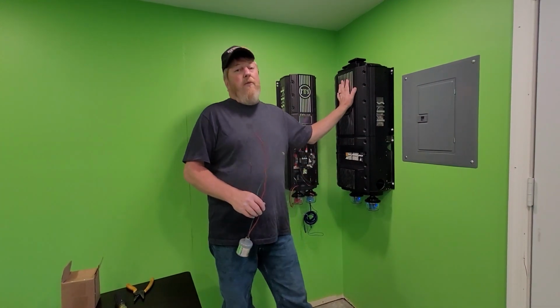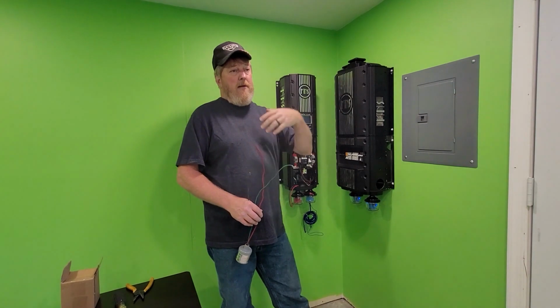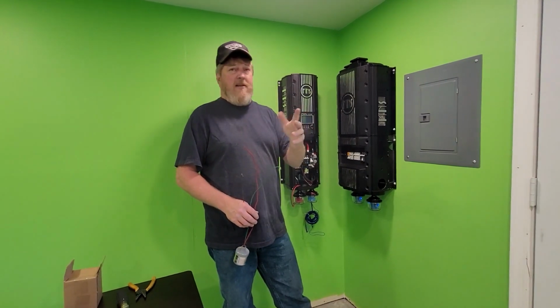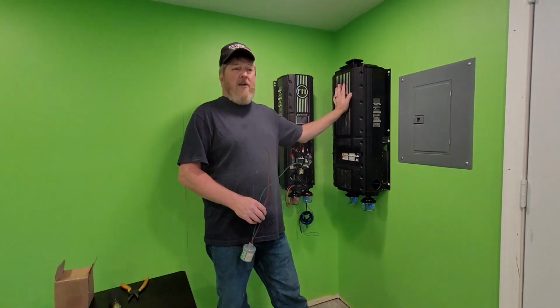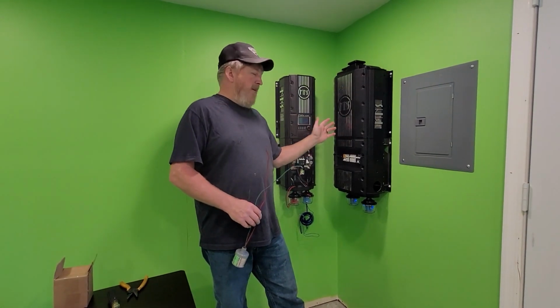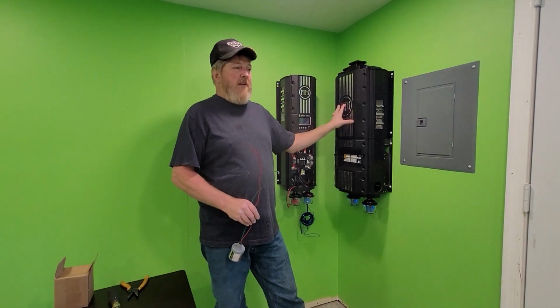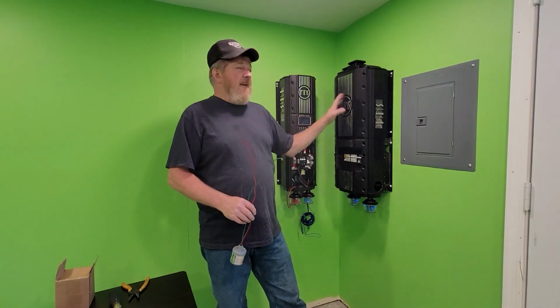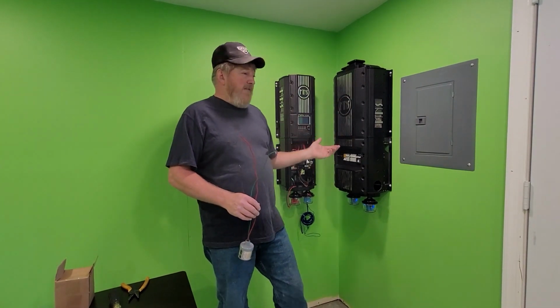When they go through UL listings, whichever NRTL, Nationally Recognized Testing Laboratory, they use, they do high pot testing, where they apply around 3,500 volts to these and make sure it doesn't leak to the case anywhere. These devices can all do that.